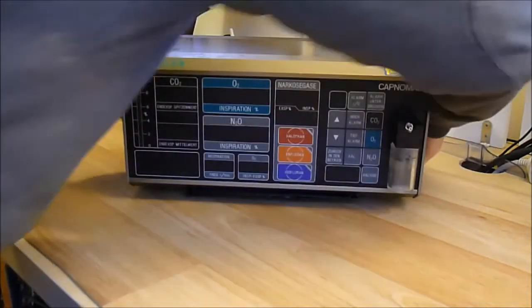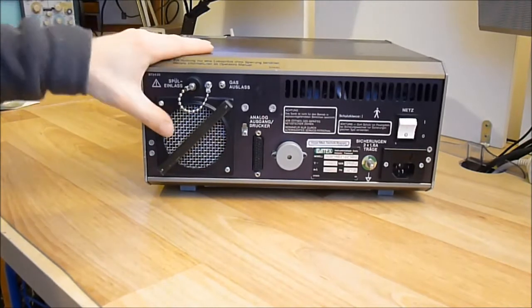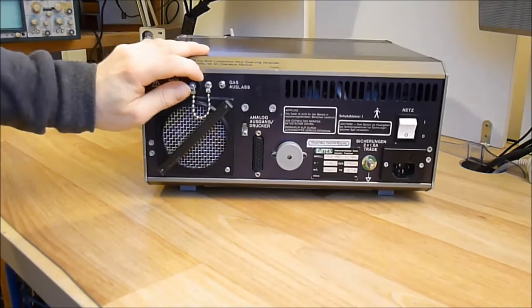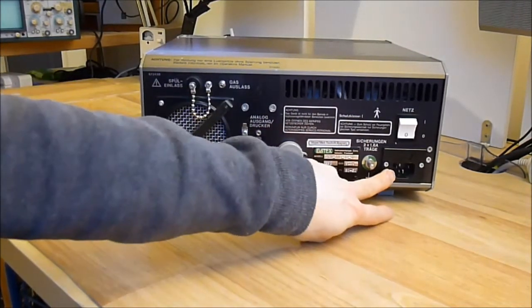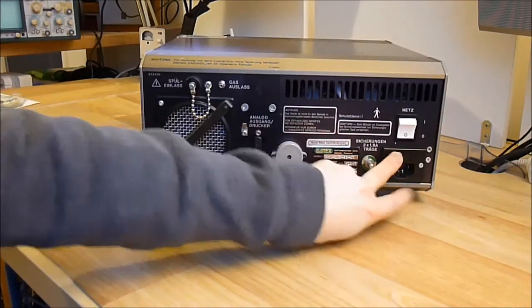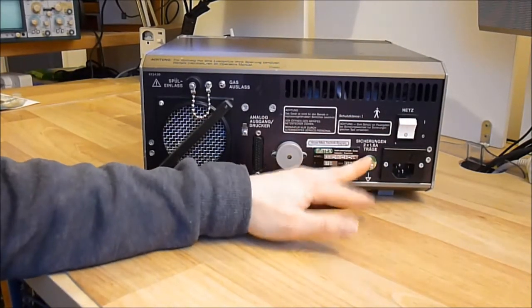On the rear side, there is not much in fact. Just a fan, some air outlets, a printer port, buzzer. The IEC port plug with medical grade with two fuses, main switch and the big grounding port here. All the manufacturer plate. So it is made by Datex Instrumentarium Corp in Helsinki, Finland. So it is quite neat.